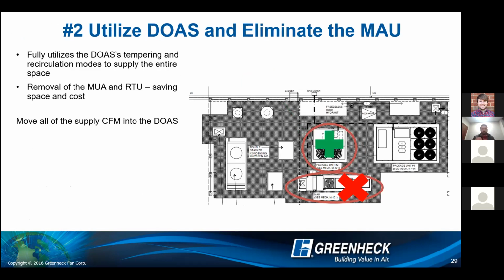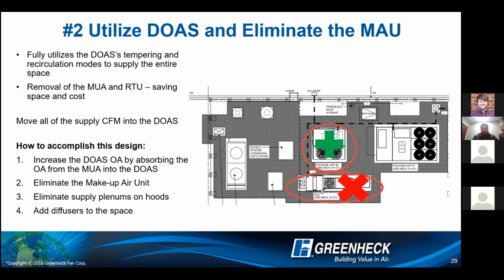The next thing we're going to do is fully utilize that DOAS and its tempering and recirc modes for the entire space. So we're going to remove the makeup air unit and the rooftop unit. That's going to save us on space and costs from the first design. Then we're going to increase the DOAS's outside air by absorbing that outside air. We eliminate the need for the makeup air unit, so that's going to eliminate that roof penetration. So you're going to have less roof space and less penetration.